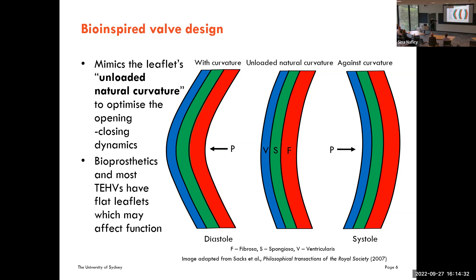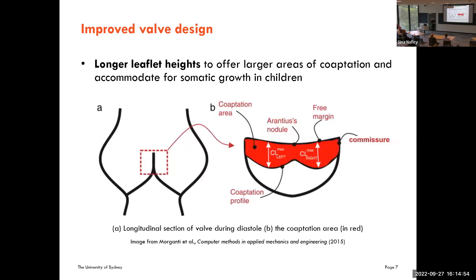Mimicking this curvature would help optimize the opening and closing dynamics of our synthetic heart valve. Bioprosthetics and most tissue engineered heart valves are developed with flat leaflets, which may negatively affect function. We want to incorporate the unloaded natural curvature. We are also looking at providing longer leaflets — to accommodate growth in children — so that as the valve expands there is still enough material for sufficient coaptation.